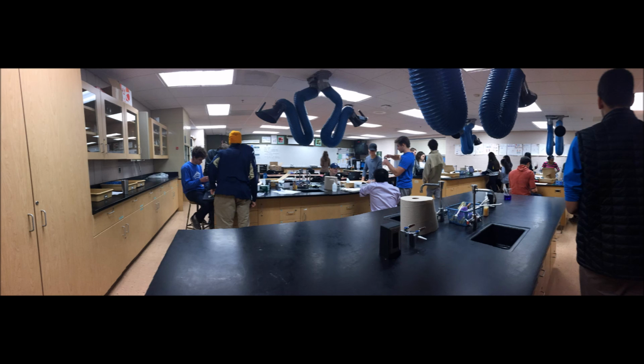A source of error in the lab is that the cuvettes are not in prime condition, specifically having small scratches on them. The scratches deflect the light, which causes lower transmittance, resulting in higher absorbance readings. This could be fixed by having cleaner, newer cuvettes.